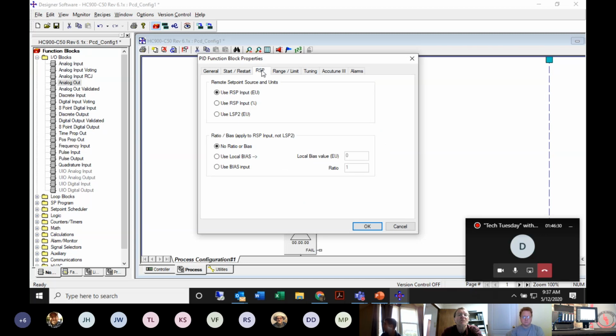Do we have a remote set point source? In this instance, no, but we could get a remote set point from another PID block or some other source if we wanted to. And we can have it be in engineering units or percent.